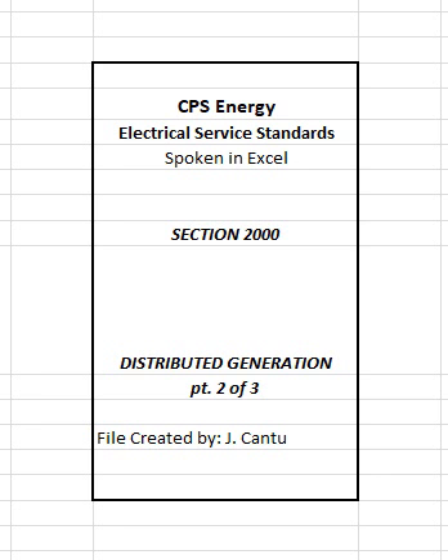E. Wiring of self-contained PV system meter sockets. Customer shall furnish and terminate all conductors within self-contained meter sockets used for PV system installations. 1. Line and load conductors in the socket must have the same ampacity rating and not be smaller than number 8 AWG copper for 100 amp single-phase meter sockets, not smaller than number 6 AWG copper for 200 amp single-phase meter sockets, and not smaller than number 2 AWG for 200 amp three-phase meter sockets.